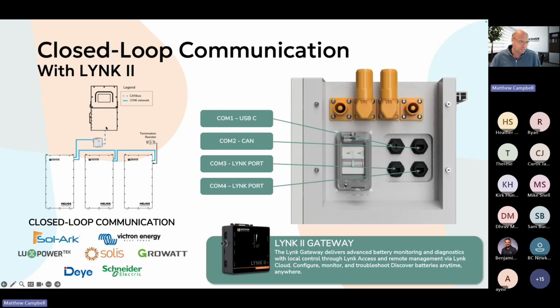And what this will do is it will actually open up communications with Schneider Electric, which you do - and we're actually testing native communications right now with Schneider, so that may be able to be done through their Insight devices. But for now, to go directly into the inverter, we would recommend that you use the Lynk 2 gateway.